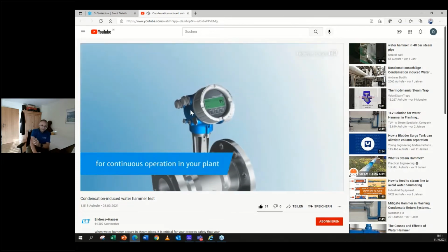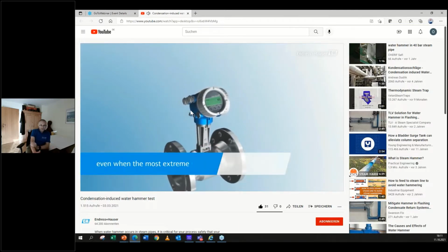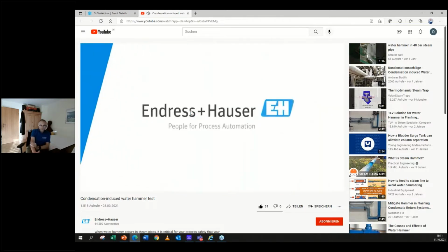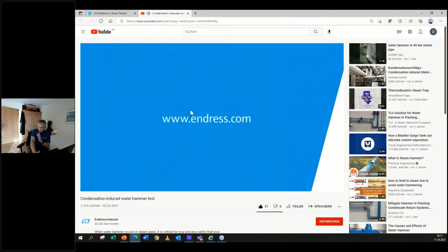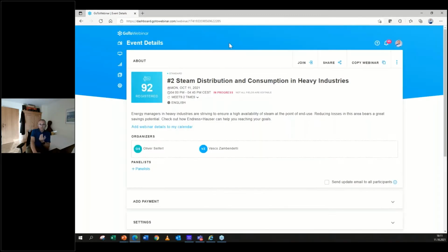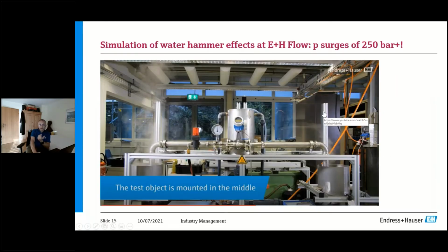So that's 100 times these 45 psi we've just seen. So 4,500 psi. This is incredible in such a low pressure steam pipe. And this is a huge impulse, of course. And even though we repeated that test various times, we got no failures of the sensors. So this is a great thing.